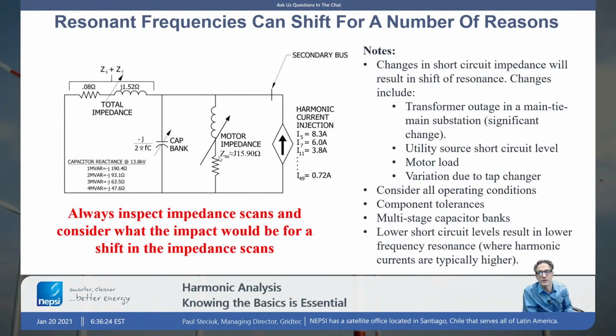So what can cause the shift? A lot of things can cause the shift. We have variable capacitance. Also, capacitor banks are built 0 to plus 10%. We have variable impedance of the source. What local generation do we have? What transmission lines are in and out of service? That can also impact the impedance of the network. And we have motor load within the plant. We all know that as we increase the motor load within the plant, the short circuit impedance goes down, or the short circuit current goes up, and therefore we will get a shift in that impedance curve. So there are a lot of things that can shift the impedance curve. We can have cable capacitance within the network that will also add capacitance to this capacitor here, causing a shift.